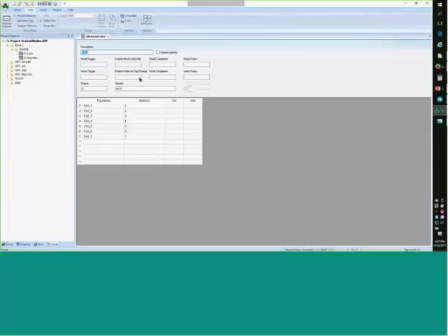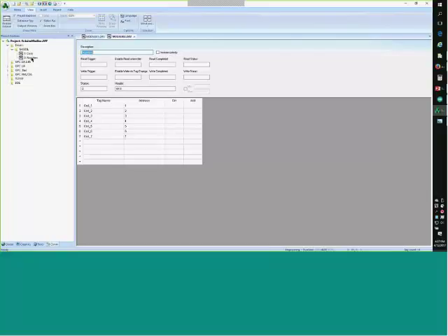Here's the coil spreadsheet — it doesn't need any kind of read trigger or write trigger. If you're familiar with Square D and understand Modbus, you know you can read and write these devices using the Modbus slave driver. Just put a station number in there and you can change coils or registers.